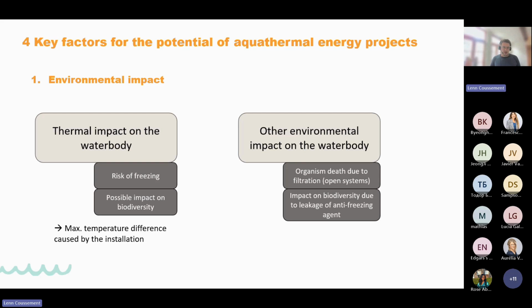The first key factor is the environmental impact, which is quite important, typically in the first place the thermal impact you might have on the water body. This happens because you take out heat from the water and supply it to your heat pump, which decreases the temperature in the water body. If you have a very big installation and a very small water body, you can have a risk of freezing.